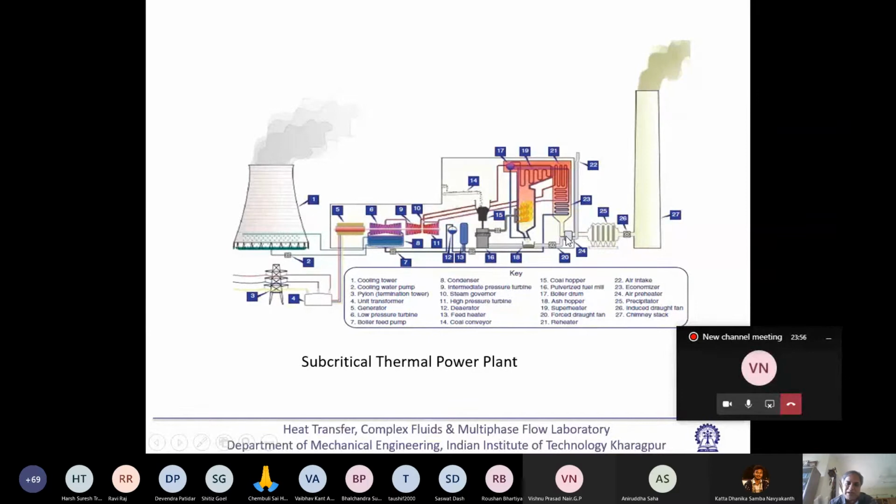Air preheater I will explain later on, I mean, how does it look and how does it operate? Sir, because there's an air preheater, we don't need a fan there for circulation? No. Air preheater will increase the temperature. Fan is needed for circulation to overcome the pressure drop. Okay. So after air passes through air preheater, then combustion will happen.